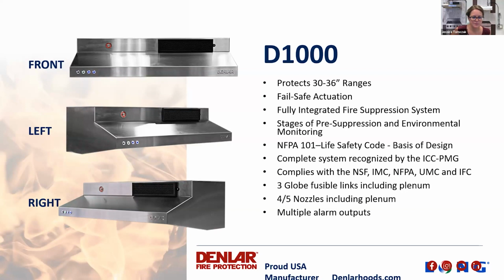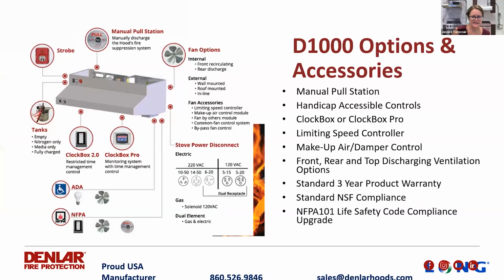We have stages of pre-suppression and environmental monitoring. We're actually trying to prevent the fire from occurring with those stages of pre-suppression: we turn on the heat fan, and in the second stage we remove the heat source as well. The environmental monitoring is designed to help protect against any risk of a fire being present when the system's not able to put out the fire properly. For example, if somebody had serviced the system and didn't connect the tank properly, it's not going to allow them to cook as part of that system.